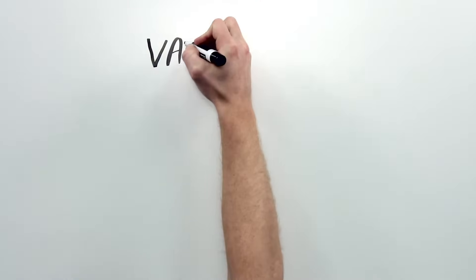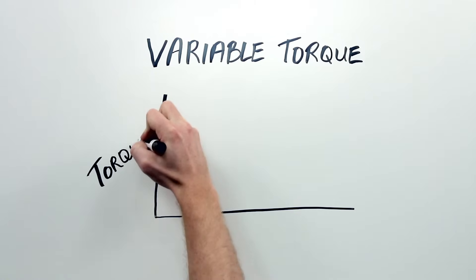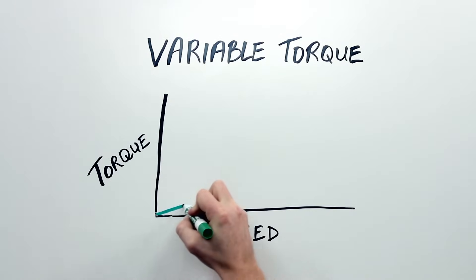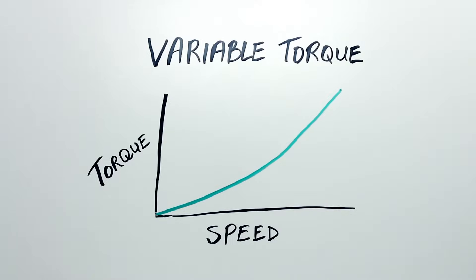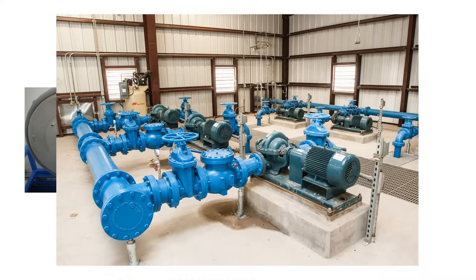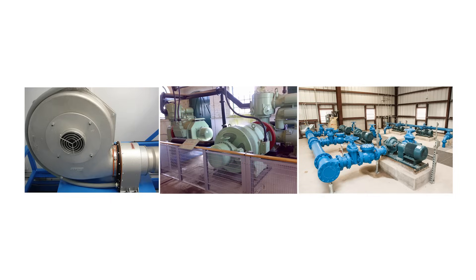Our fan example is what's called a variable torque load. As the fan speeds up, the amount of torque or force required to move the air increases. Other types of variable torque loads besides fans are blowers, spinning pumps, and spinning compressors. The general rule of thumb is that if the load being moved is air or a relatively easy to move liquid, like clean water, then it's likely a variable torque load.